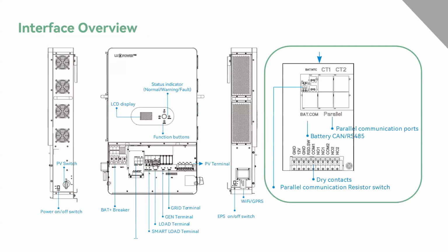Okay, so after that, let's take a closer look at the inverter itself. From the right side, there is a PV switch and the power on and off switch, and in the front side, there is an LCD display, the status indicator, and the function buttons. And we have the battery breakers and the battery terminals here, the communication ports here, and the smart load terminals, both of them come with a breaker. And the GEN terminals, the grid terminals, also the earthing terminals, and the PV terminals here, two MPPTs, and each MPPT supports two strings.